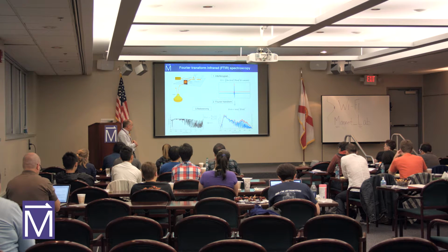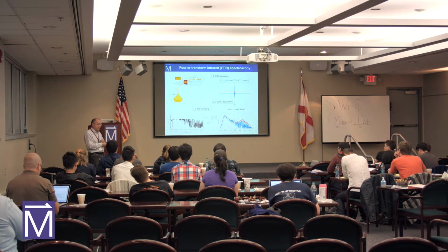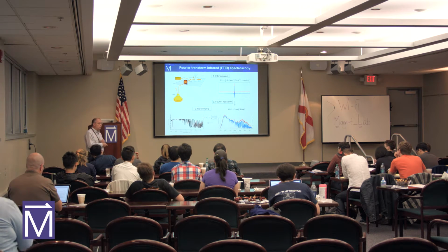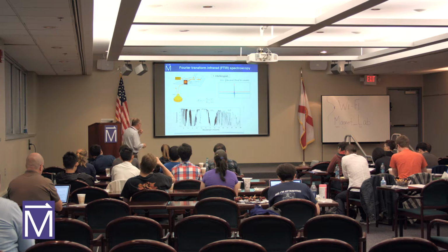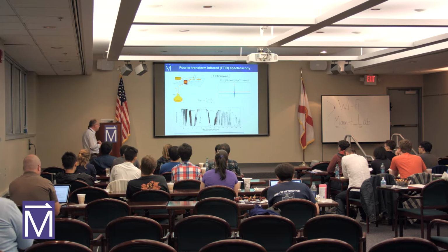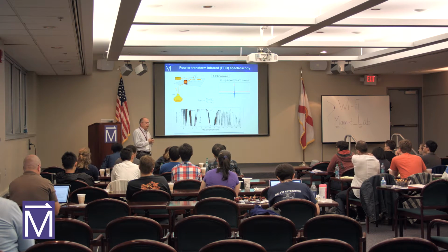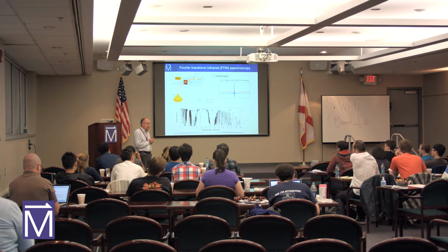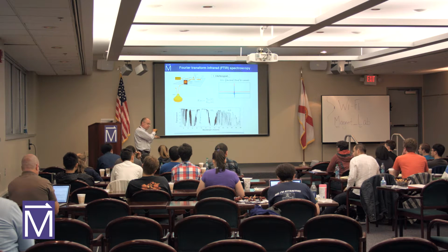Let's perform the Fourier transform. Red is the spectrum of the reference, blue the spectrum of your sample. You divide and you recover beautifully the absorption spectrum, actually the transmission spectrum of air. All these are water lines. They are real. It's water vapor in air. Not only water bothers us for IR spectroscopy, but also CO2. That's why the IR spectroscopy setup has to be vacuumed. It always has to be pumped to at least about 1 millibar, from the spectrometer, all the path for the IR light to the sample and then back to the detector.